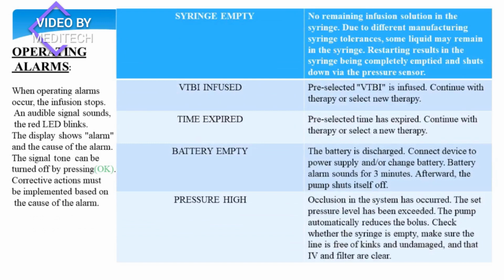Syringe empty. No remaining infusion solution in the syringe. Due to different manufacturing syringe tolerance, some liquid may remain in the syringe. Restarting results in the syringe being completely emptied and shuts down via pressure sensors. VTBI infused. That means the pre-selected VTBI is infused. Continue with therapy or select new therapy. Time expired. Pre-selected time has expired. Continue with therapy or select a new therapy.